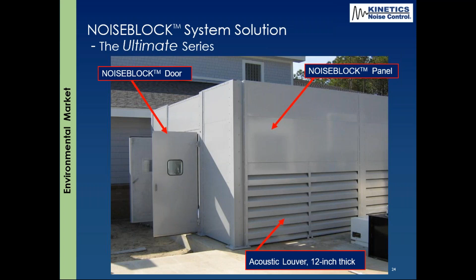Another view here, kind of seeing inside - the acoustical consultant had looked at lining the walls of this air-cooled chiller equipment yard to control the noise. The problem is the design could only get about 8 to 10 dBA, and we needed a lot more - we needed about 16 dBA reduction. So that's why we had to go to this system.